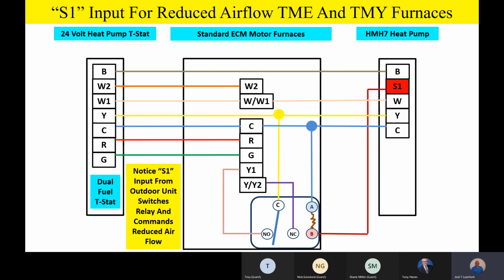So same routine as before. Remember that S1 is an output, a 24-volt output from the outdoor unit to switch a relay to command reduced airflow on the indoor product. Any questions or comments on how we're hooking these products up utilizing that relay kit and the logic of that relay? Oh, by the way, while I'm on this line of thinking, if you take a look at that outdoor unit, unlike some heat pump products, to get full functionality on the indoor product, we only need 5 wires outside. Go ahead and count them. 1, 2, 3, 4, 5. B, S1, W, Y, and C.